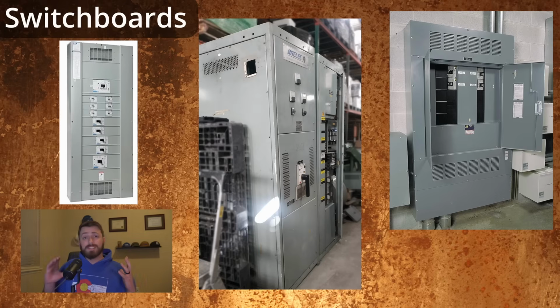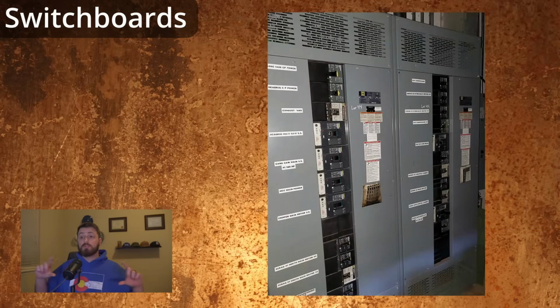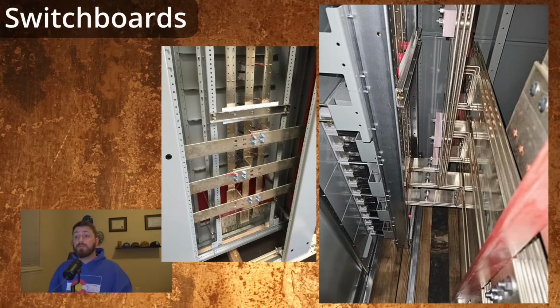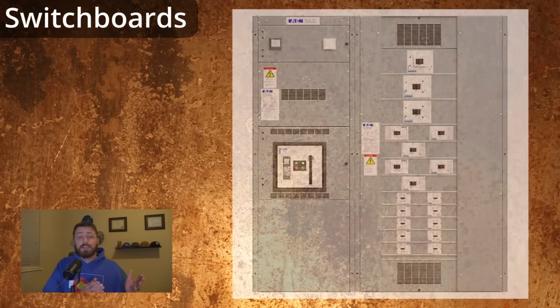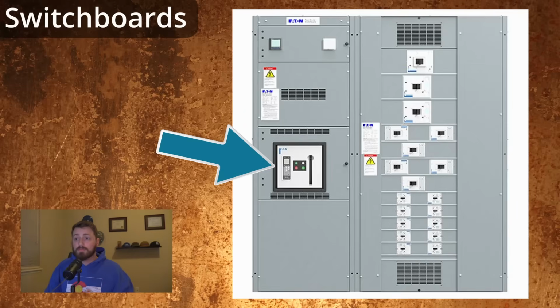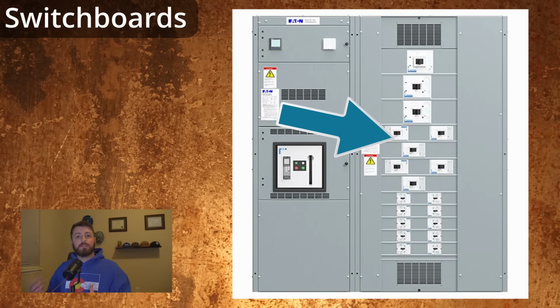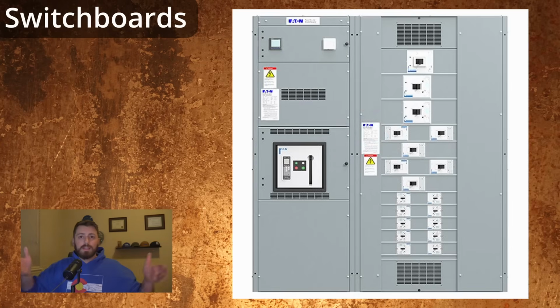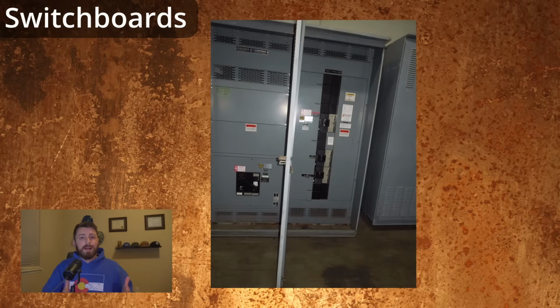These can have multiple distinct vertical sections with large bus bar mounted horizontally connecting between them. For modern installations, you'll often find the main section will contain one large insulated case power circuit breaker or a huge fuse disconnect switch, like a Pringle switch or something like that. The other sections will have vertical bus connecting to the feeder breakers, similar to a panel board. Sometimes it'll actually just look like a panel board is mounted inside the vertical section of a switchboard. Big differences between this and a panel board are that a switchboard will almost always be sitting by itself on the floor and may be accessible from the rear or the sides to pull cables in and terminate up to the breakers.